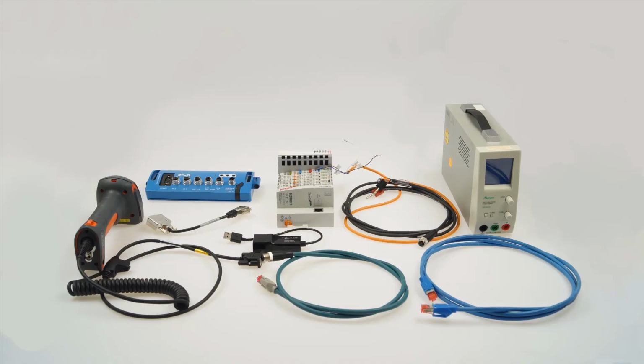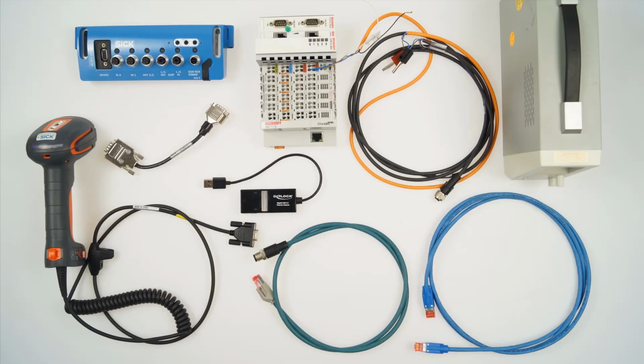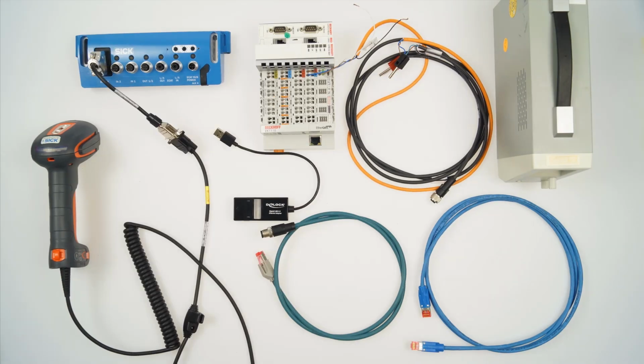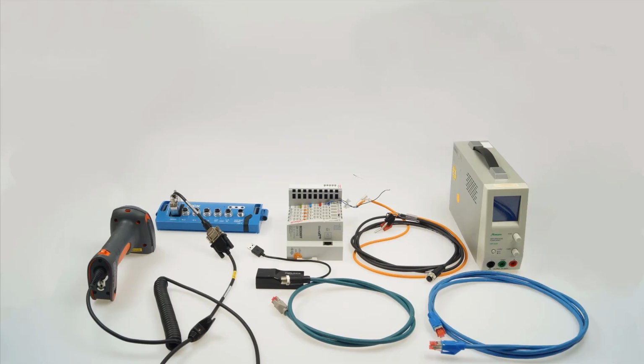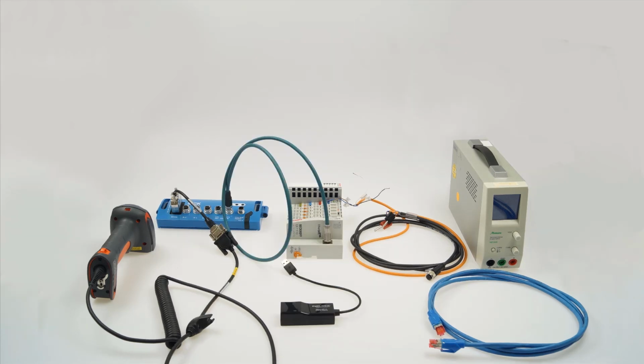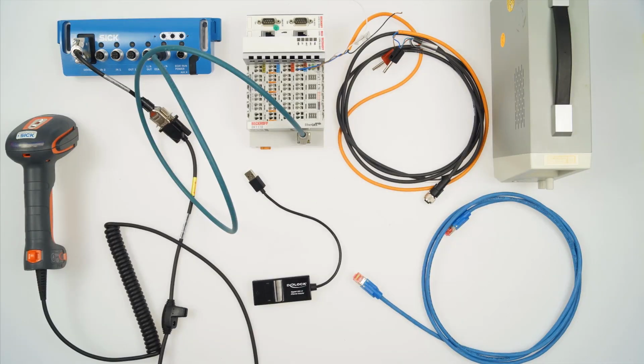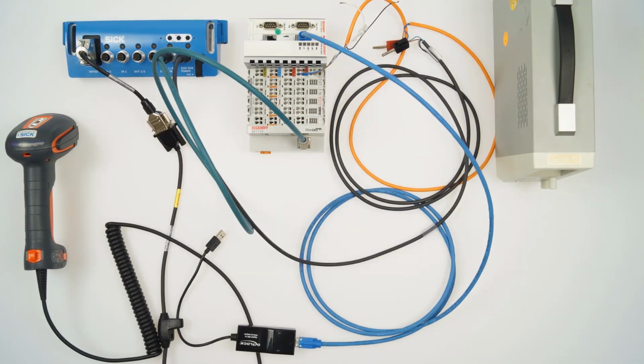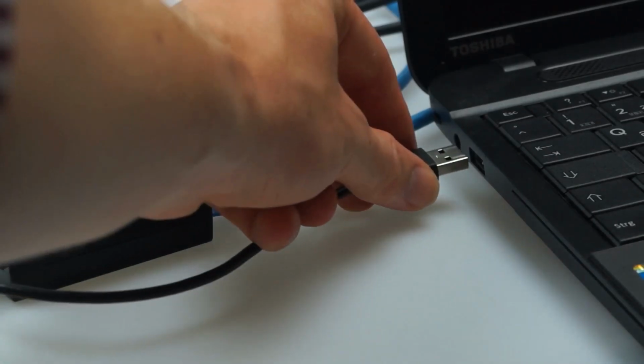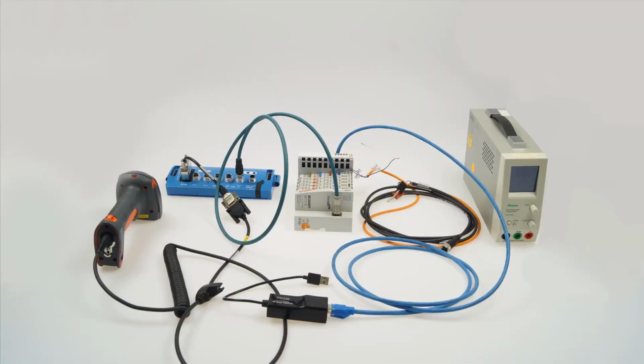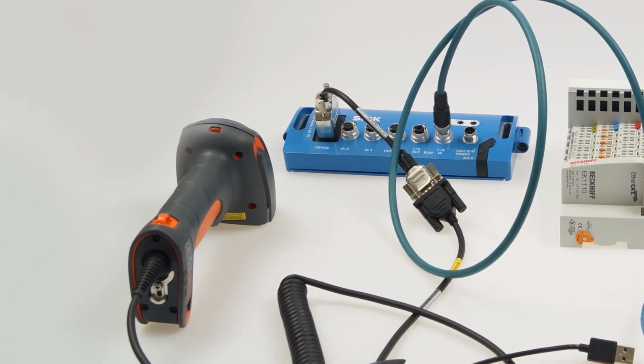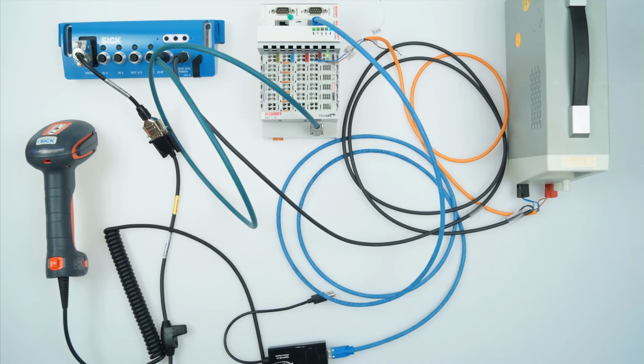Commissioning of the hardware. Connect the handheld scanner using the scanner connection cable and the adapter converter to the RS232 socket named device of the CDF. Then connect the CDF with the EtherCAT terminal device using the EtherCAT cable. The Beckhoff CX9010 PLC is connected to the PC via Ethernet cable plus converter. The handheld scanner is powered by the CDF via pin 9 of the adapter converter.